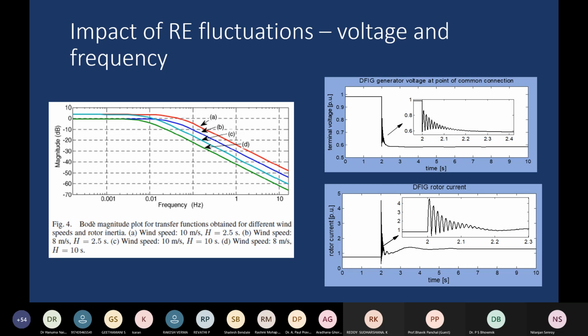So the grid actually comes out with different grid codes, and in India also we have a similar kind of grid code that mandates that if you want to connect to the grid, you need to be able to remain connected even if there is a temporary under voltage situation or an over voltage situation. So therefore you need to take action inside your generator to protect itself without disconnecting, so that it is able to inject active or reactive power into the grid during the voltage sag.